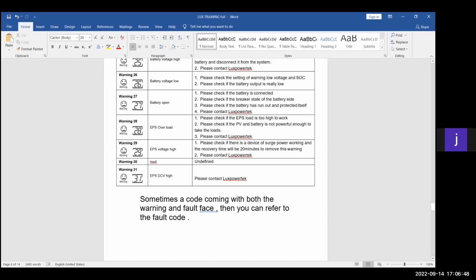So when you have a system that is communicating with a battery, you'll see a lot of times error 27, and the inverter shows there is voltage. As soon as you have a battery that communicates, your battery sends its voltage via the communication cable to the inverter. So that gives the inverter an estimate or the exact value of the voltage of the batteries. So if it's a battery that communicates and you get 27, then you can just check your fuses and everything to make sure that your battery is physically giving out power.